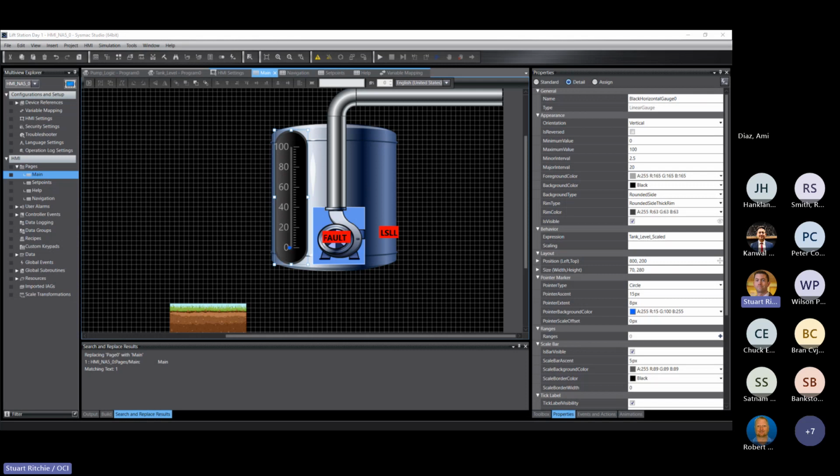Okay, now we will create some buttons on the HMI for local control of the system. So you might be remotely viewing this screen from a different area. You don't have access to the physical start, stop, and reset push buttons. So we will add our own stop, start, and reset push buttons to the HMI. And we will have to add some tags in the PLC as well, because, like I mentioned before, we can't write to a digital input. It will just be overwritten every scan cycle with the physical digital input signal.